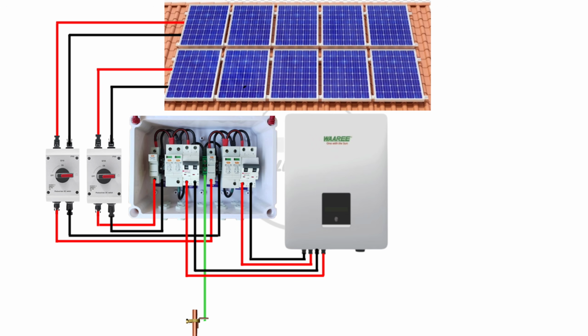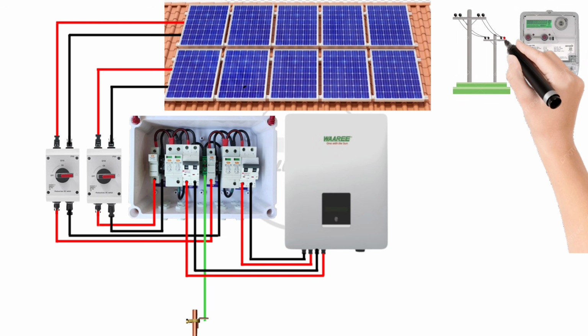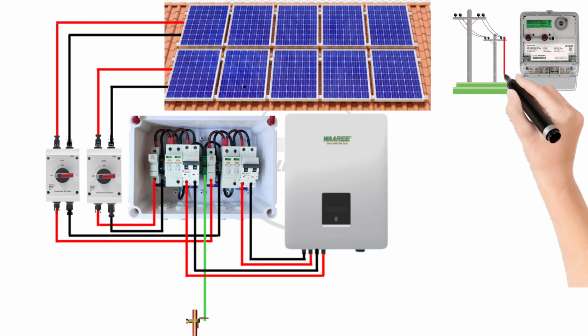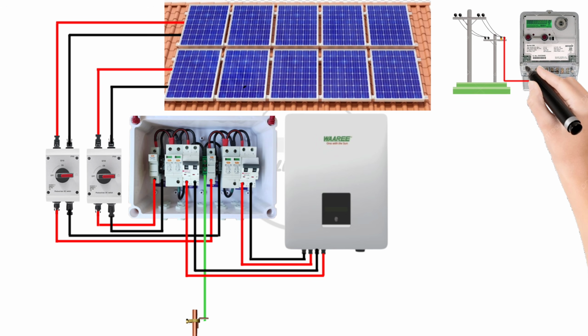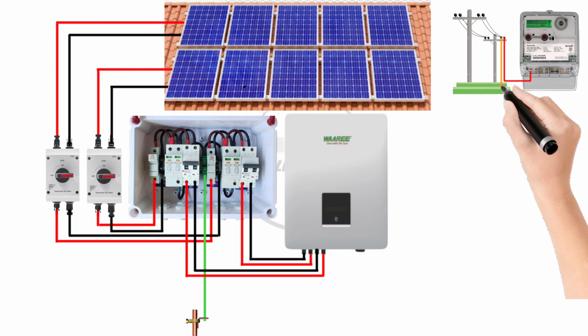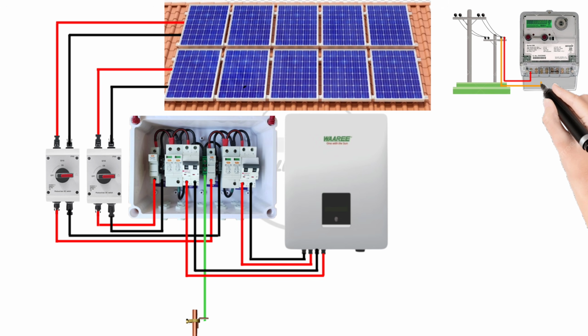How to connect a 5 kW AC side grid tied solar system. Now I will cover the wiring from the 3-phase grid supply all the way to your inverter. Let's take a look at the overall wiring diagram. We will be connecting our 3-phase grid supply to the energy meter, then to the disconnect switch, voltage protection relay, SPD, MCB, and finally to the inverter. First we connect the 3 phases RYB, L1, L2, L3 and a neutral from the grid supply to the input terminal of the energy meter.